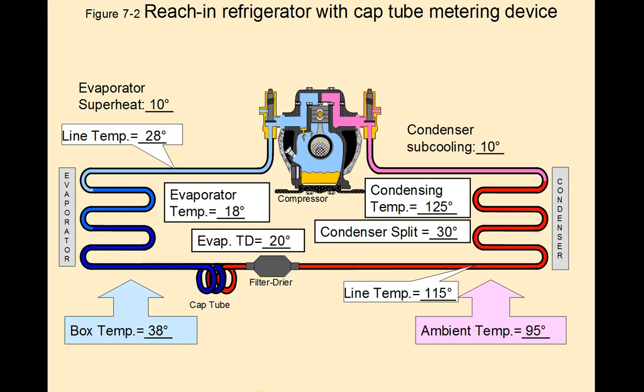So here we have a 95 degree ambient with a line temp of 115 degrees, and if you notice, the condenser split is 30 degrees, and the condensing temperature is 125 degrees, and the subcooling is 10 degrees, which is pretty much in line with the TXV or TEV system. The condenser splits and the subcooling are measured the same way as you do it in any other system.